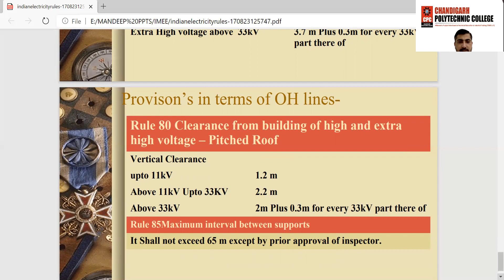And under Rule 85, maximum interval between supports. The supports or mechanical supports used to carry the overhead conductor shall not exceed 65 meter except by prior approval of the inspector. It means the interval or span between two poles, the maximum length from one pole to the second pole, is 65 meter.